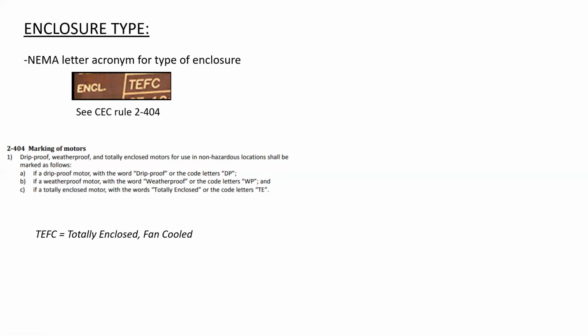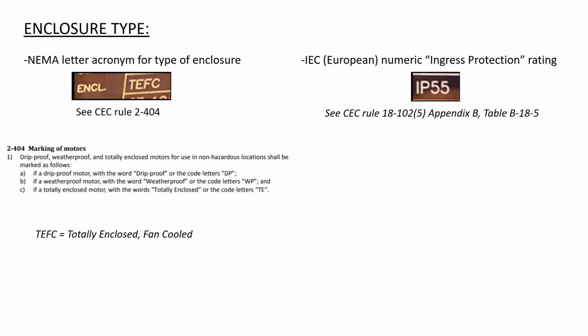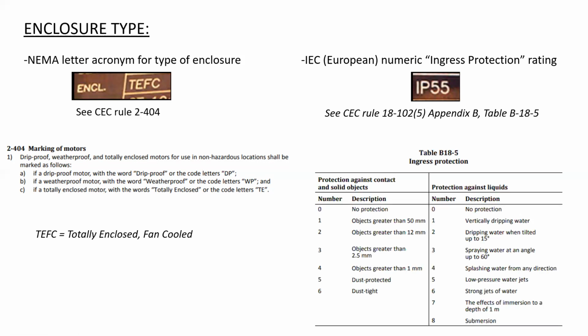The other type of enclosure rating, almost parallel to the NEMA letter acronym, is the more European numeric ingress protection rating. We can find information on this in the CEC in Appendix B, 18102, Subrule 5, Table B18.5. This provides us with a very standard numeric rating system. The first number indicates the protection against contact and solid objects. The second number indicates the protection the equipment has against liquids. We see that this particular motor has a 55, which means it's dust protected and protected against low pressure water jets.